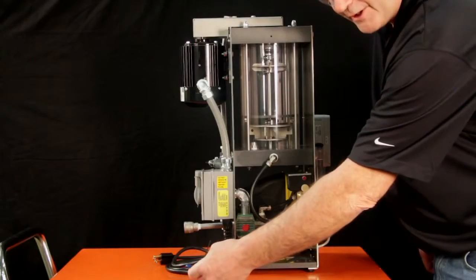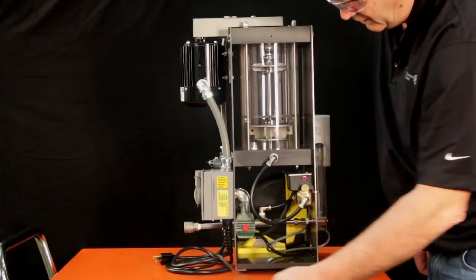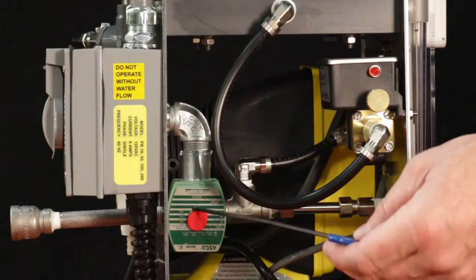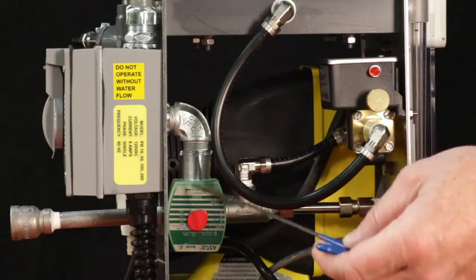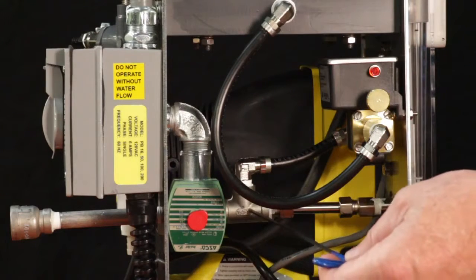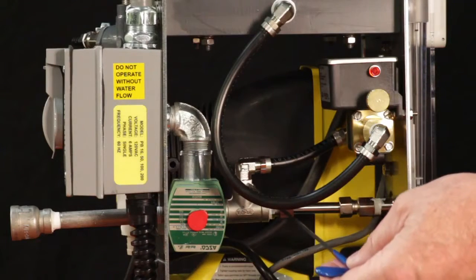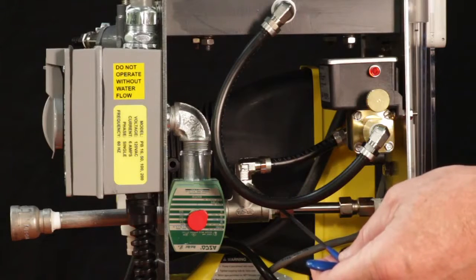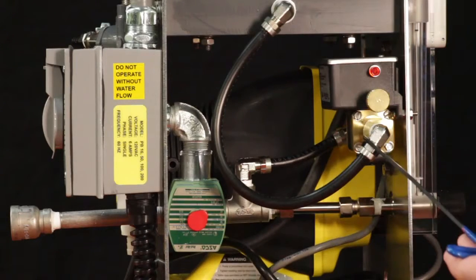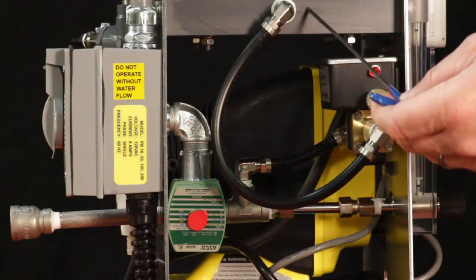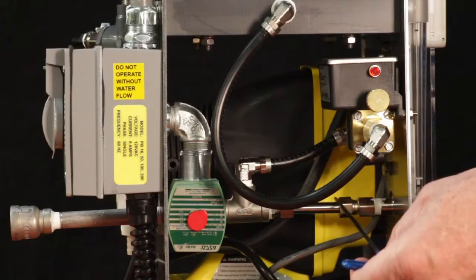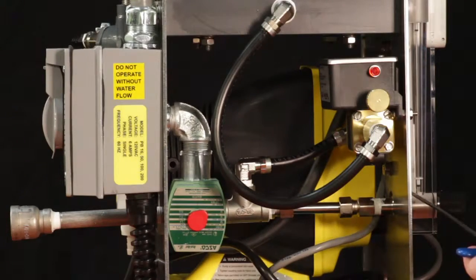Located on the back of your unit is your water inlet. Your water inlet goes through an electrical solenoid. Water is established to the T. On the T, you'll have the high side of your differential pressure switch. On the opposite side of your differential pressure switch will be your low side, being measured inside the actual mix chamber. From there, water goes through to your flow meter.